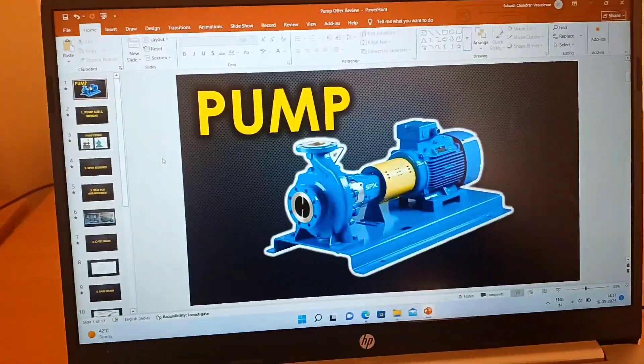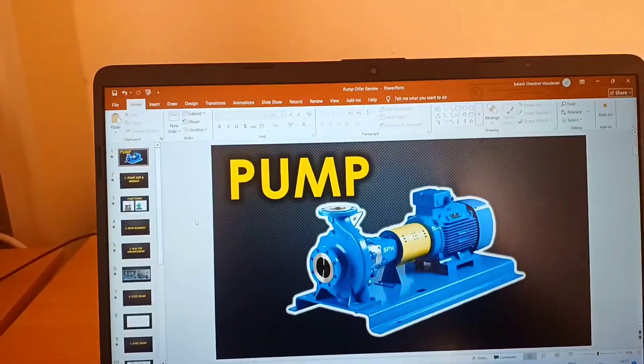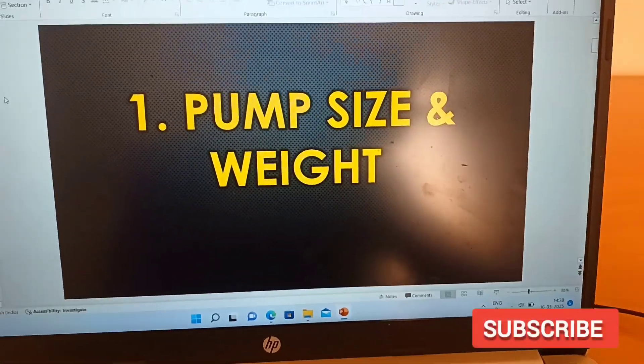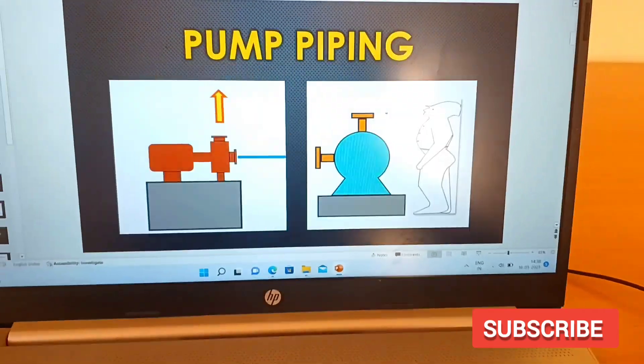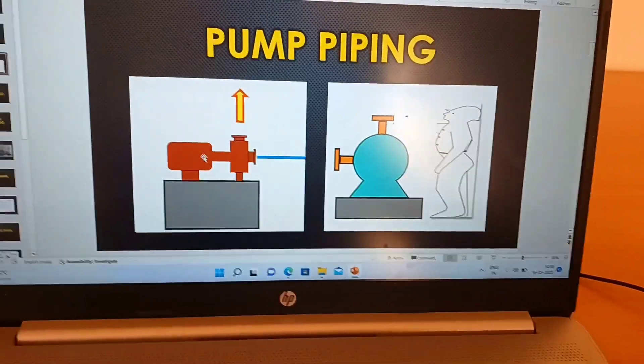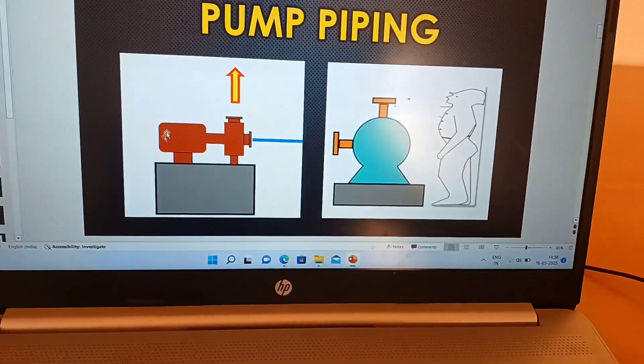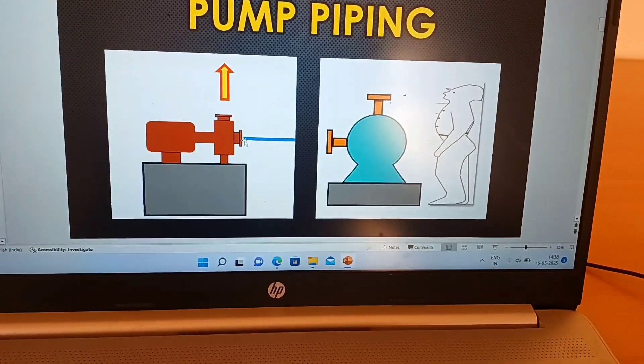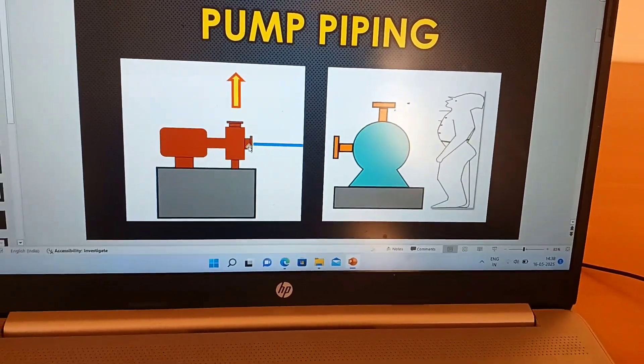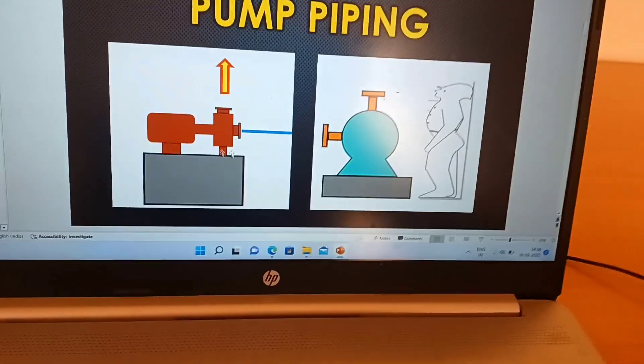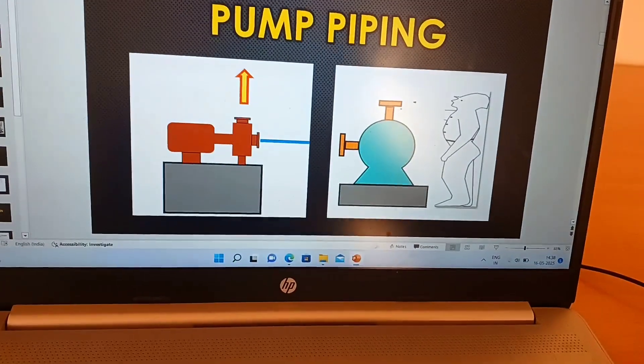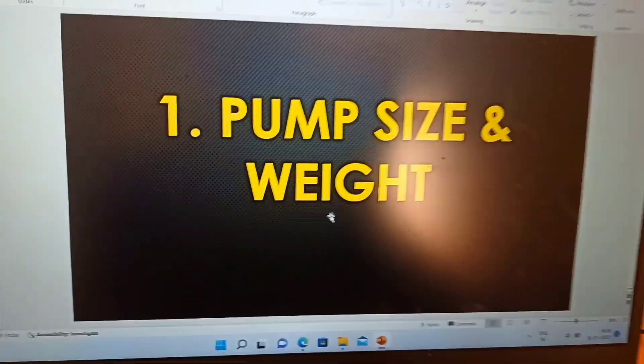Let me show you how this works using the PPT prepared for you. The first most important thing to check is the pump size and weight in the vendor drawing. You need to check pump size and weight because it relates to various other inputs — for example, unless you know the pump size, you will not be able to finalize the pump centerline elevation, and you will not be able to size the foundation if you don't know the weight and overall size.